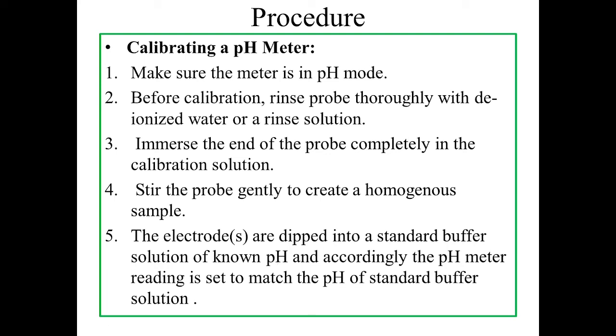Say you know that the pH of the buffer is 4, and you check it on your pH meter. If your pH meter shows 4, no problem, your pH meter is showing an accurate reading. It is already calibrated. If it is not showing 4, you have to adjust the primary calibration knob such that the displayed reading becomes 4.